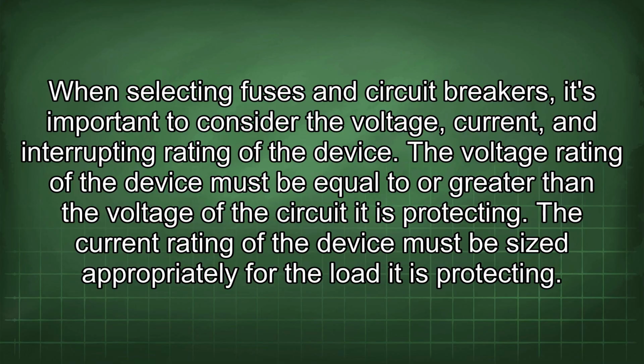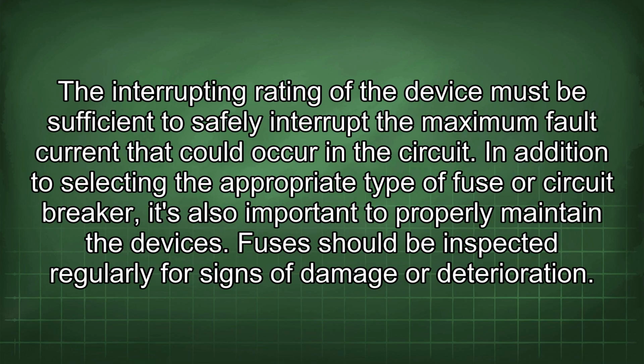The voltage rating of the device must be equal to or greater than the voltage of the circuit it is protecting. The current rating of the device must be sized appropriately for the load it is protecting. The interrupting rating of the device must be sufficient to safely interrupt the maximum fault current that could occur in the circuit.